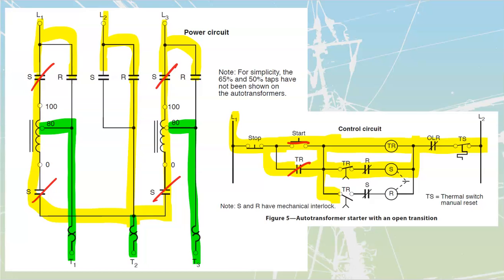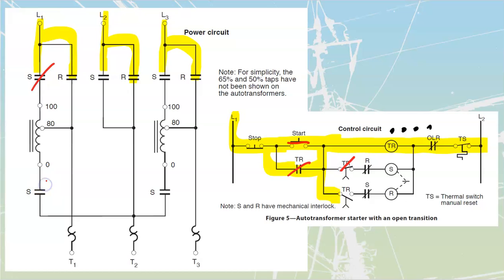In the meantime, we just accomplished all of that action. This timer over here, when we powered it up, is an on-delay, so it's doing its timing action. At the end of its timing action, it is going to close this one while simultaneously opening this one over here. So for a brief second, while that one is opening and this one is closing, we're going to lose all contactors and all paths of current to the load. It's an open type of transition, which means that we're going to be coasting on our motor just for a brief second. And then, because it's in the middle of process changing, and this is all happening across milliseconds, this is going to close.